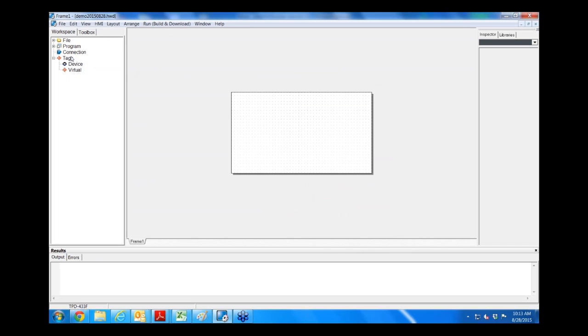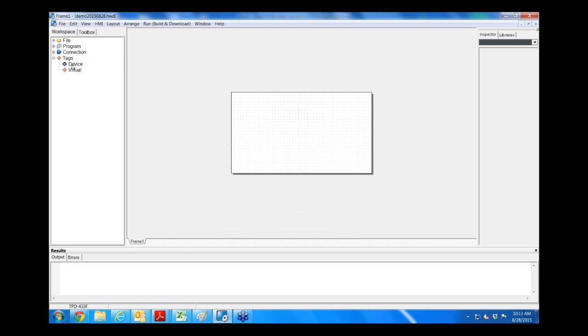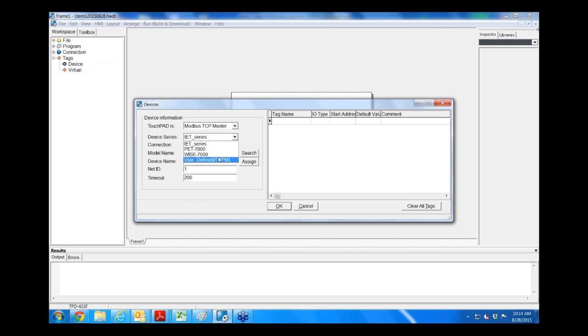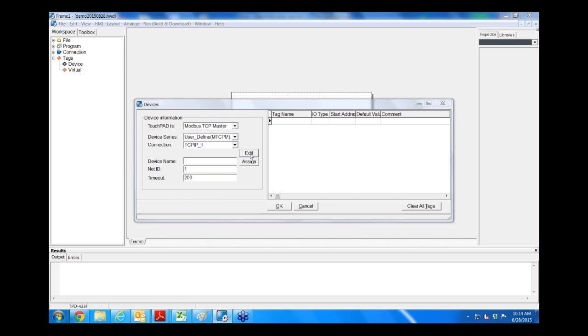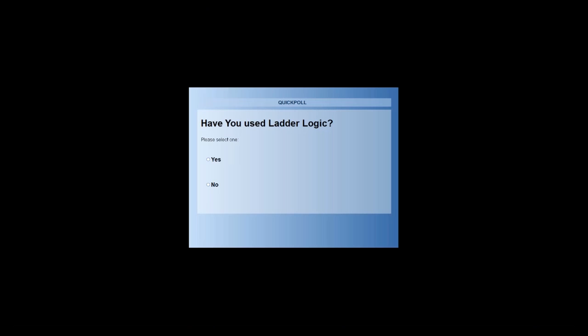The first thing we must do is create a few connections to devices and a few tags so that we can implement the logic. So for instance, let's just create a Modbus TCP connection. So we'll create a Modbus TCP connection from the touchpad itself, and then we'll create a device with some tags. For this one, the touchpad will be a Modbus master. I'm going to assume that we have a third-party Modbus device, and just do user-defined at the bottom. You click on edit to assign the number of each type of tag. Let's just put five of each, and then we have five digital outputs, five digital inputs, five analog inputs, and five analog output channels to use in our logic.